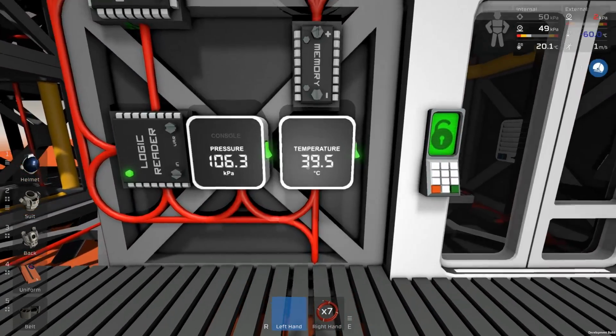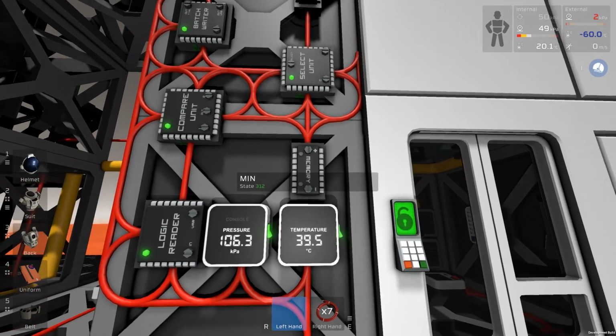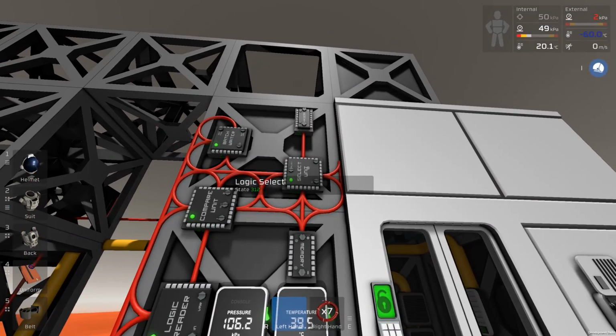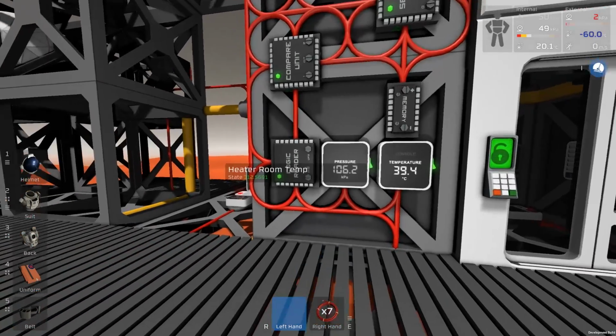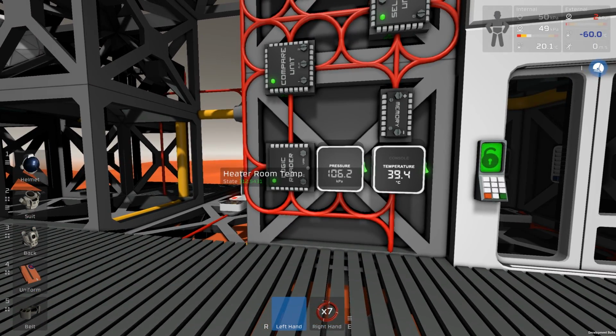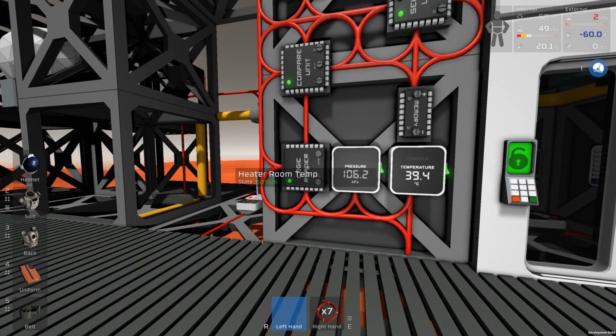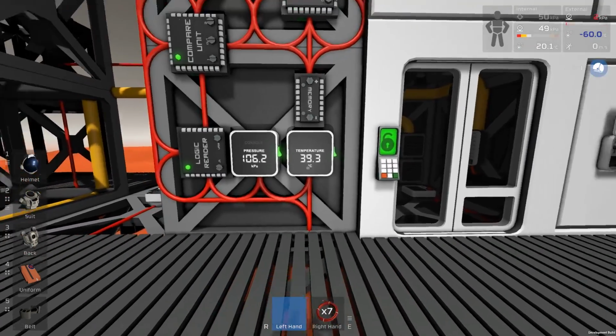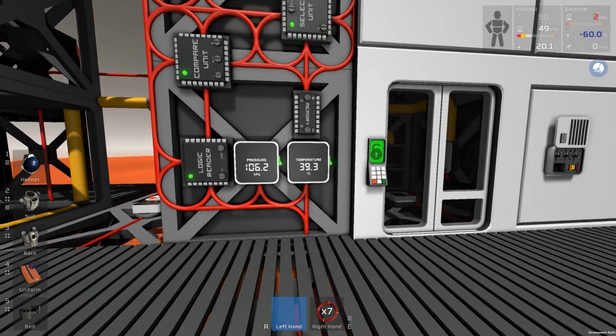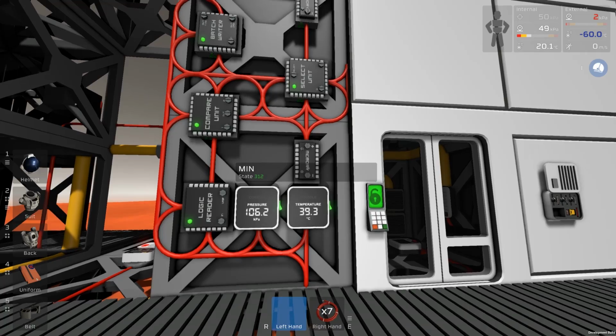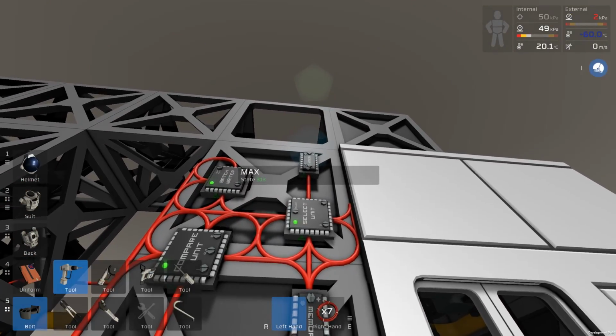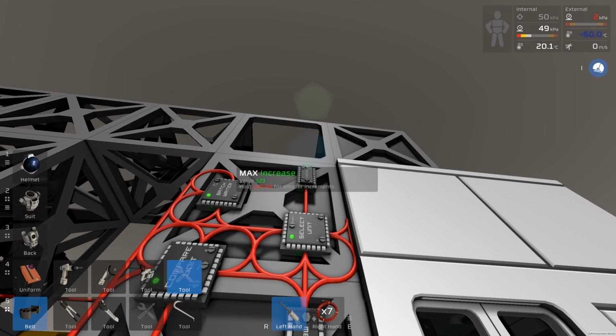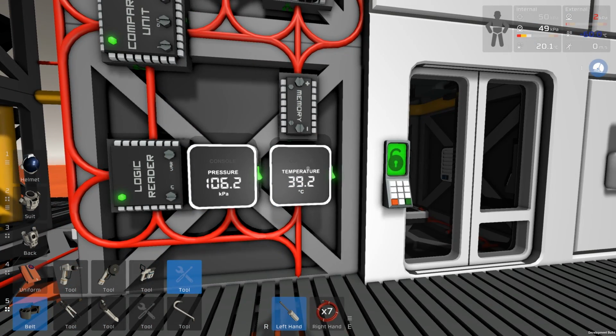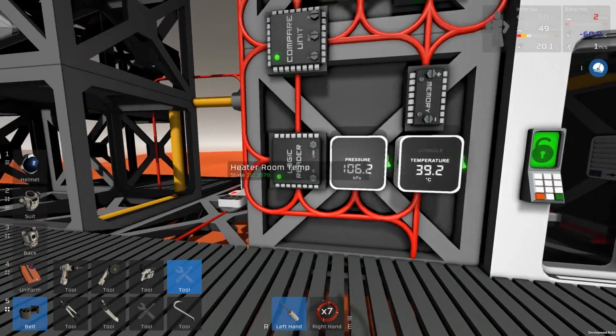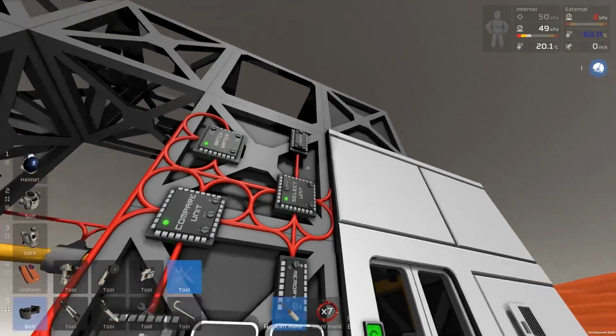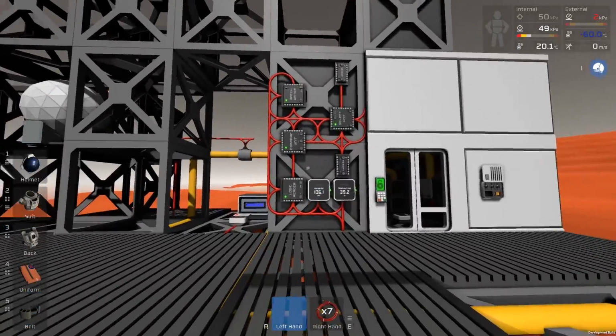And the room itself is 39.5, so clearly it's not quite accurate just yet, but I'll play around with that next time. And yeah, what's the room temperature at the moment? Yeah, 312. It has triggered already, so it's just keeping it between 312 and 313, so that's 39 degrees. So 39.5, I was accurate. There we go. So if we want to change that, we just change the upper bound and fall all the way back to 39 and whatever. So if I just change that, up that to 373 now, the next time it falls below the minimum value, it will heat, and then only turn off when it reaches that top value. It won't turn on immediately, just because of how the whole system works.